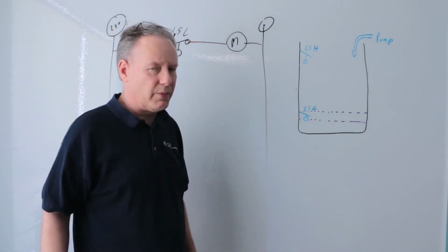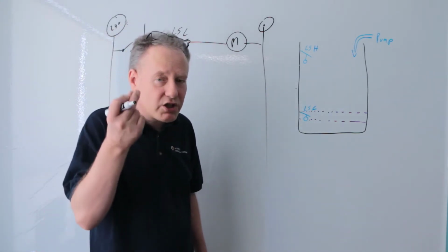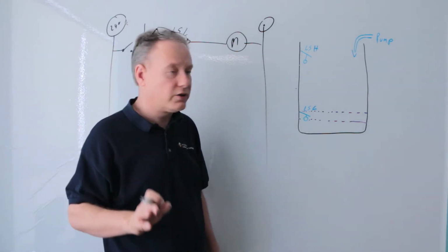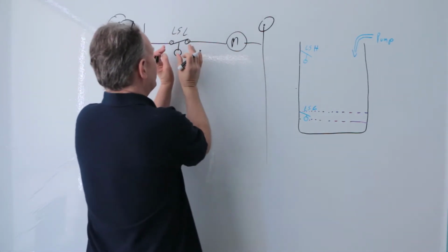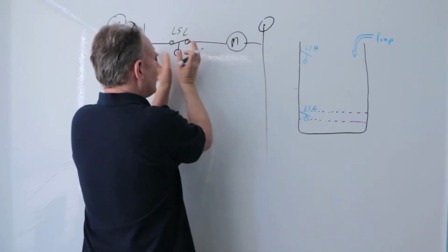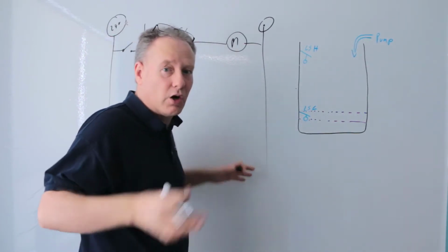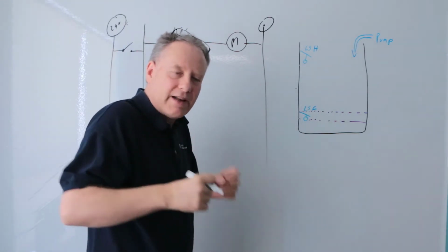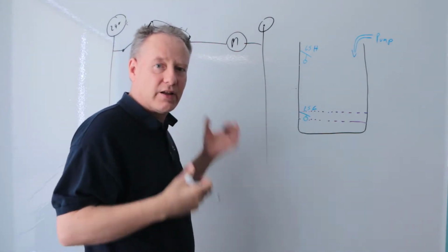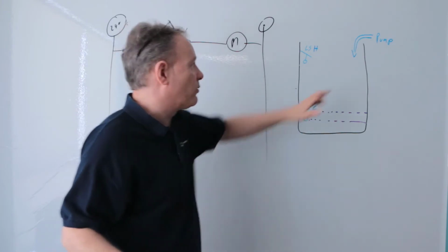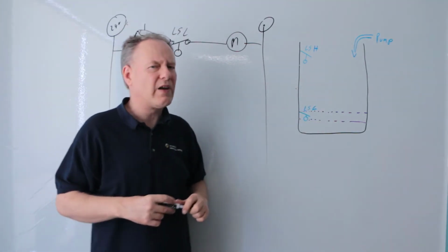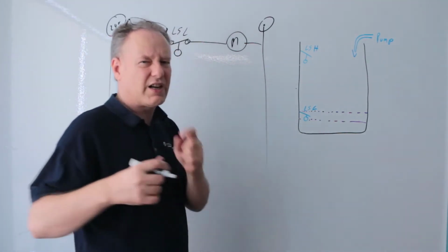Now, there are a couple different ways to do that. My first go-to, in my brain, would be to latch onto this, to put a memory latch onto this, a holding circuit. Remember this event happened. Even if the event goes away, the memory latch is going to hold on to the action that event originally made happen, which is turn the pump on. So that would be my first go-to. So let's actually just do that.